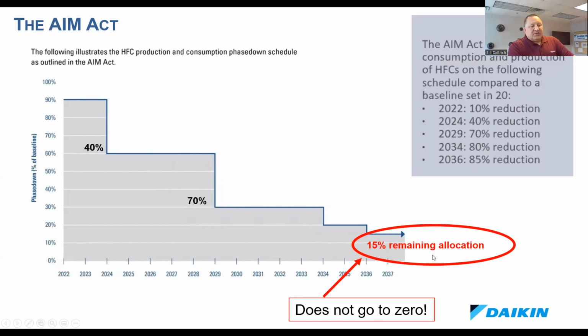The thing that's interesting is when we phased out the CFCs and HCFCs, production basically went to zero. Under the Kigali Amendment and the AIM Act, there's going to be a 15% allocation remaining, so there'll be a service tail to make some refrigerants. That's good news overall and addresses a lot of the concerns we saw with the CFC and HCFC phase out. There'll be a 15% remaining allocation for new equipment or new production, plus reclaimed and recycled refrigerant will always be available as well.